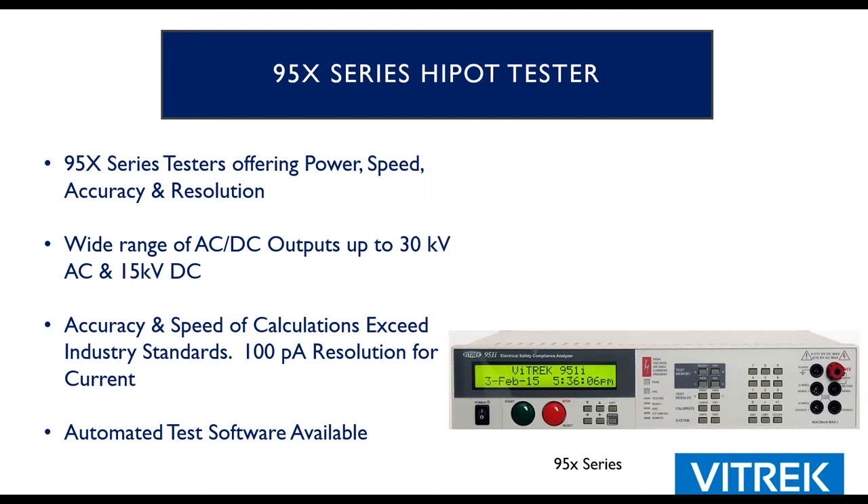The other family is the 95X mainframe — very flexible, with multiple voltage output options: 6, 11, or 15,000 volts DC; and 6 or 10,000 volts AC with an external option up to 30,000 volts. If you need speed and precision, this is the top tester on the market. Test times can be 100 milliseconds or less depending on voltages. The leakage current resolution is 100 picoamps, with total accuracy measurement of about 1.5 to 2 nanoamps — unprecedented for most hipot testers. This accuracy also allows IR testing to about a teraohm.